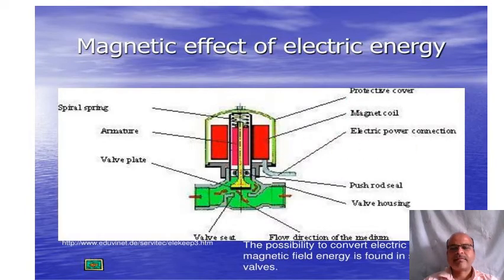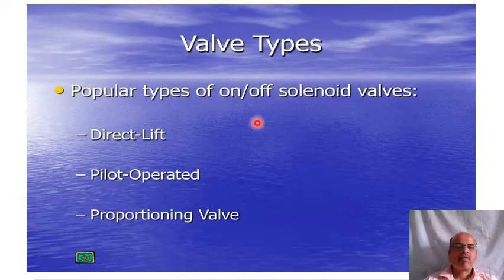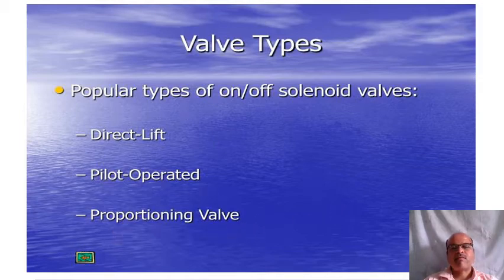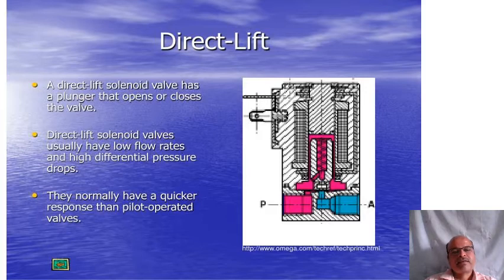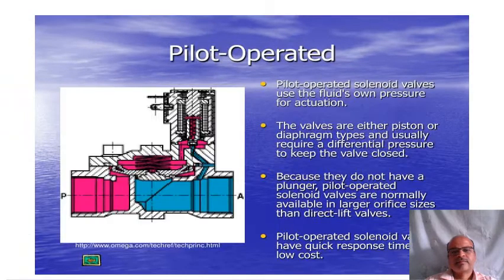The popular types of on-off solenoid valves are: directly operated, pilot operated, and proportioning valves. In a directly operated solenoid valve, a plunger directly opens or closes the valve. These usually have low flow rates and high differential pressure drops, and normally have a quicker response than pilot operated valves.